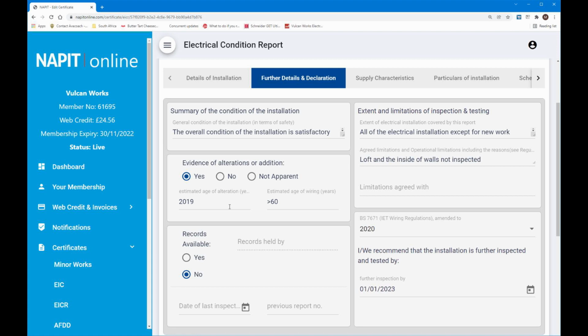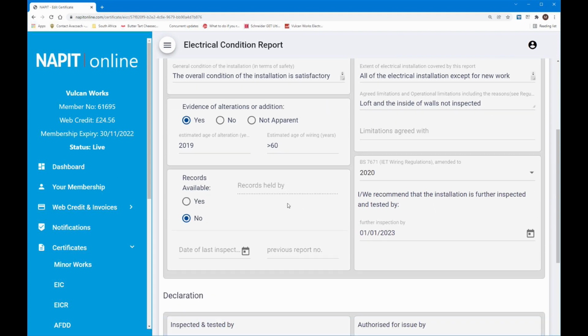Now we do know from the client that there were alterations or partial rewiring done a few years ago. That's the reason why this report was done, because it was not done in a satisfactory way, at least not as far as the client was concerned. I was brought in to do a thorough look over, and you'll see what we found in the video and what goes in this report. The wiring that hasn't been changed is about 60 years old. This property was built 1930s, 1940s we reckoned, so that'd be about right. There are no records available. No inspections have been done in the past, so there's nothing to say there.